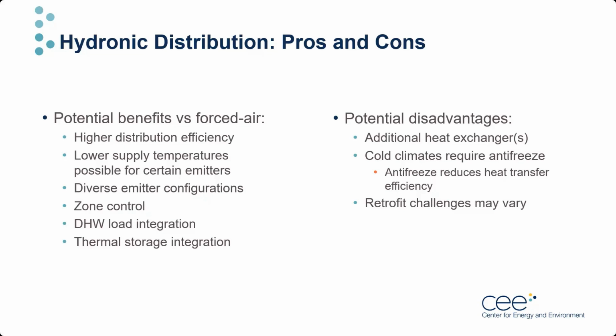This is of particular concern with in-floor radiant heating, where, as you might imagine, contractors and homeowners are rightfully cautious to avoid freezing and bursting within the slab. This isn't always needed, however, as systems without hydronic lines outside the envelope or in unconditioned space wouldn't have a risk of freezing, but contractors and homeowners may still elect to add antifreeze for peace of mind, as was the case in our installs. And finally, hydronic distribution may pose some site-specific challenges in retrofit scenarios as well. This includes retrofitting homes with higher temperature distribution systems like high-mass cast iron radiators that are designed for supply temperatures that are much higher than can be achieved with a heat pump. And with that, let's turn the page to our next section, where we'll look at the types of air-to-water heat pumps on the market.